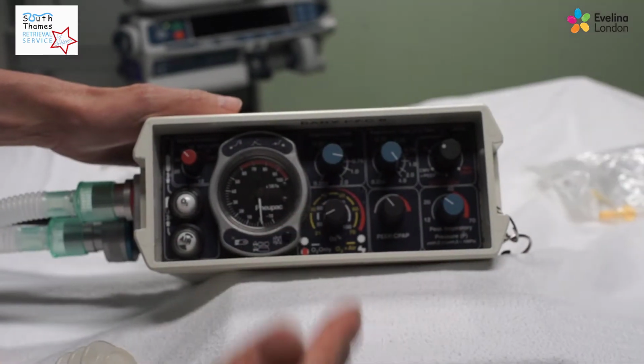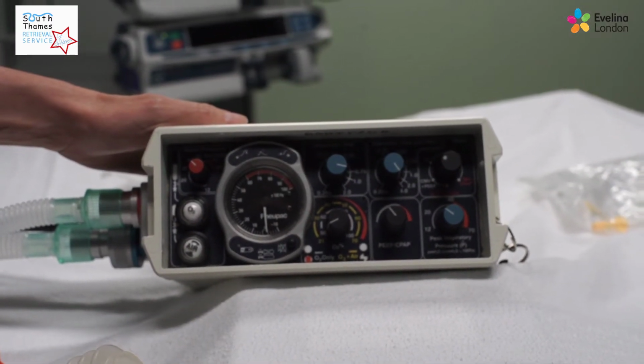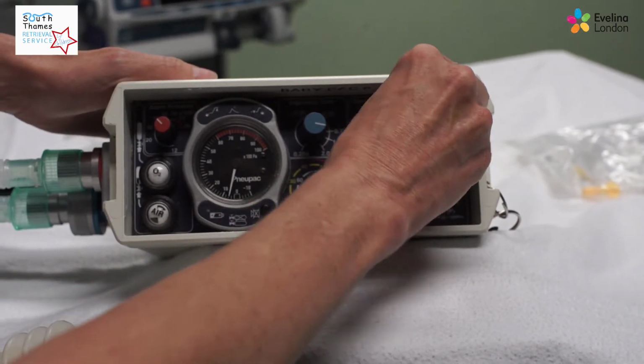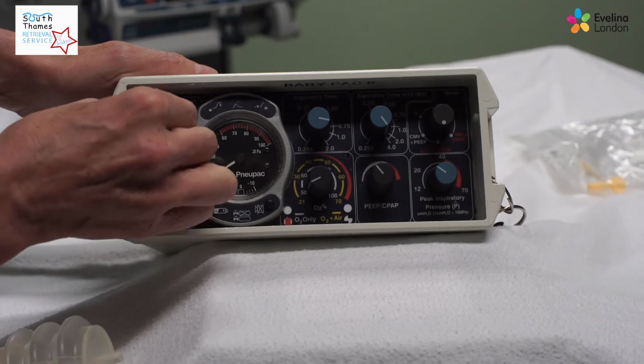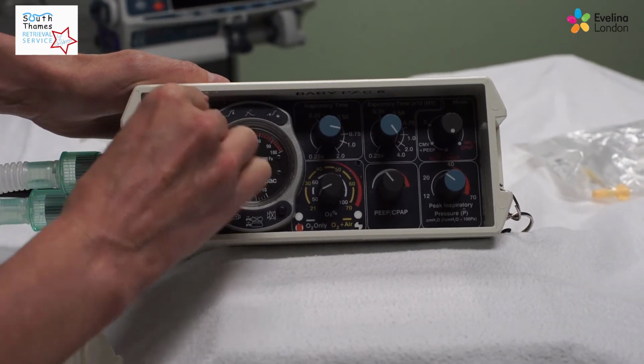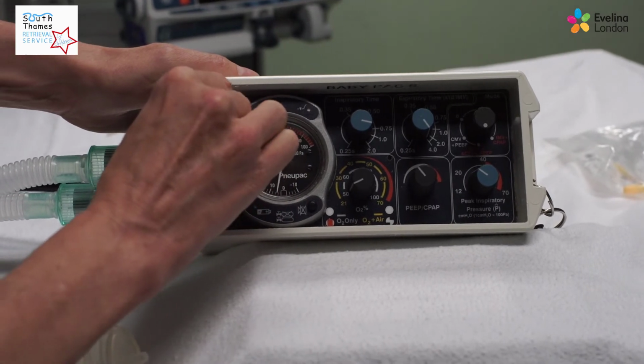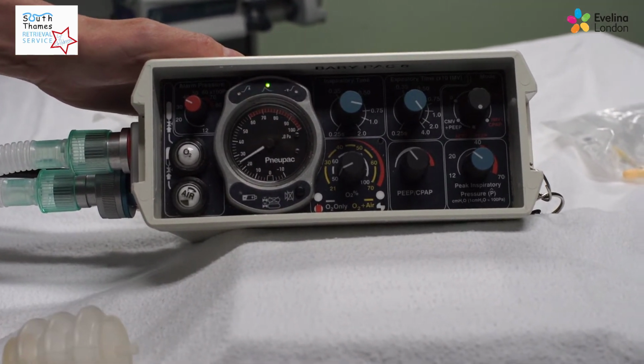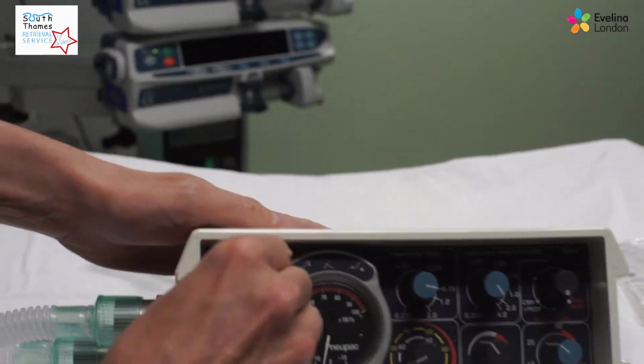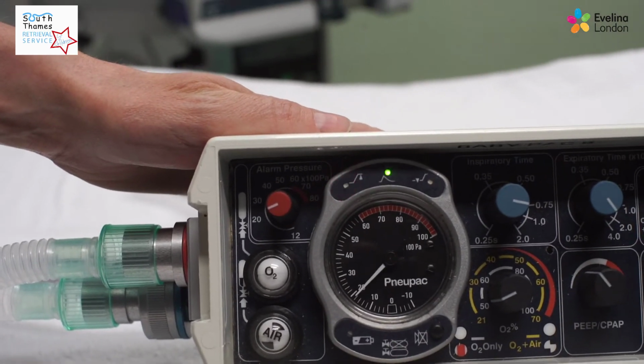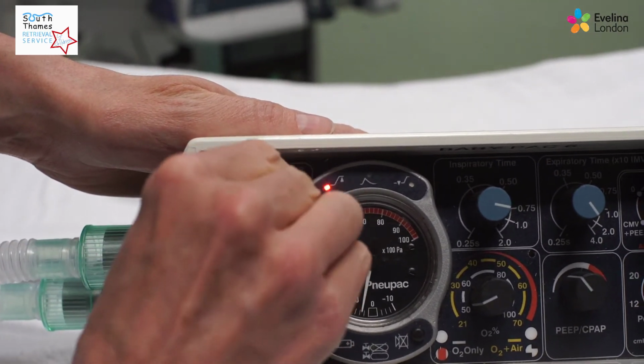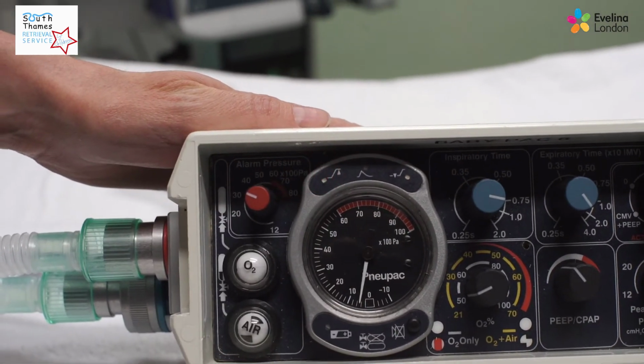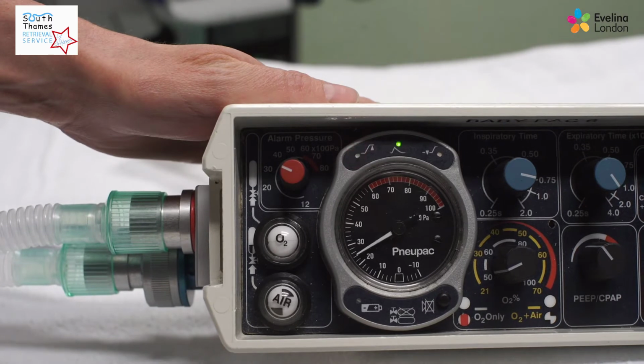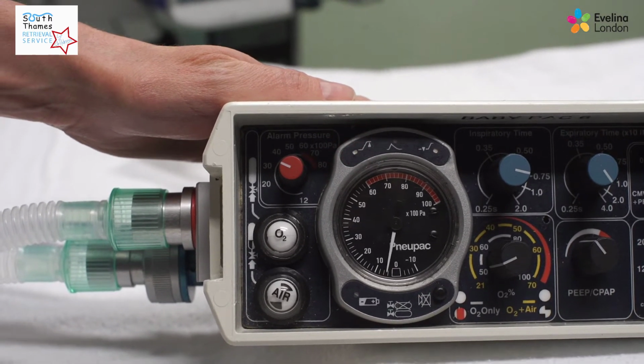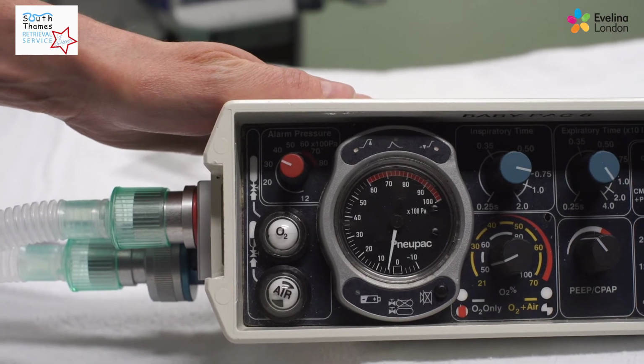The Babypac comes with alarm limits to prevent the child from having too high ventilation and damaging their lungs. The peak alarms are set using this dial, and it also limits the amount of pressure that you can ventilate with. If we turn this alarm right down, it will alarm and tell us when the ventilations go above 18. We're happy for this child to have higher than that ventilation, so we turn it up and it allows the higher ventilation to occur and doesn't start alarming at us.